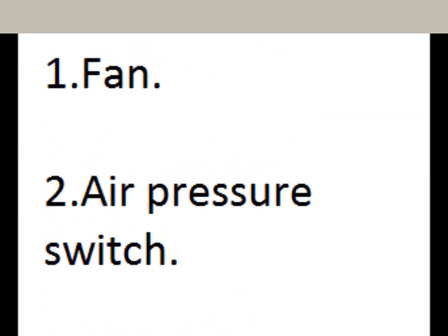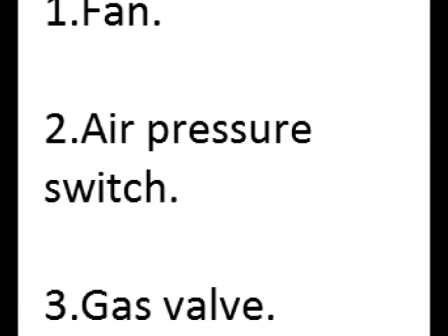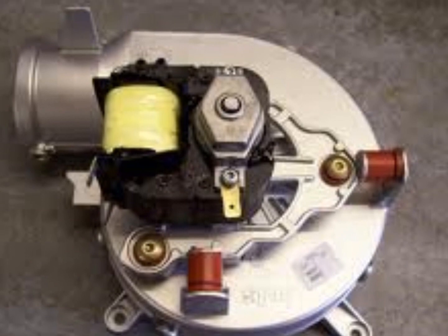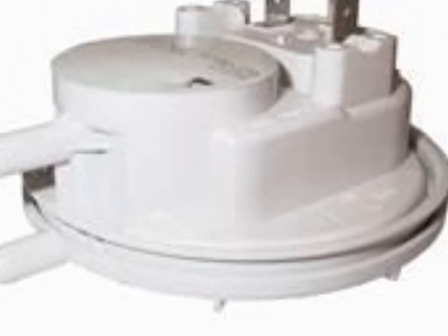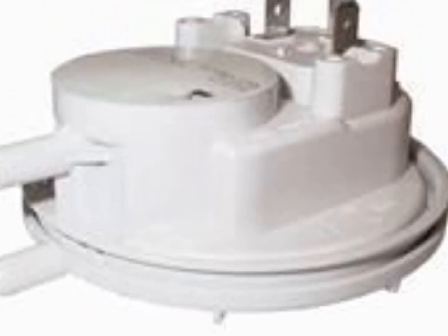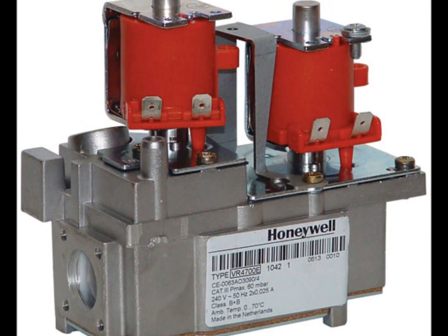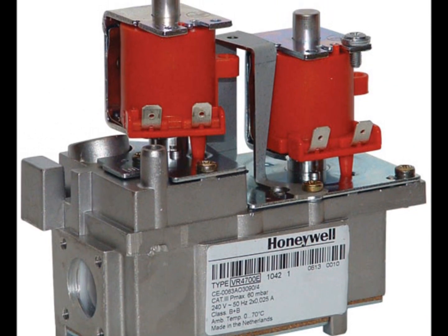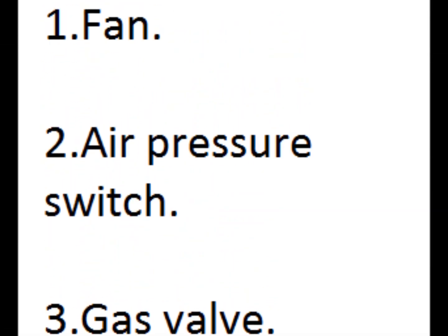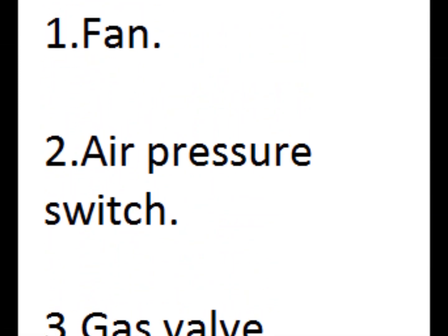The first thing that actually happens is the fan — the fan runs. After the fan comes the air pressure switch. After the air pressure switch comes the gas valve. These are the three fundamental things in boiler repairs. If you don't know this, you're not going to be able to repair it.